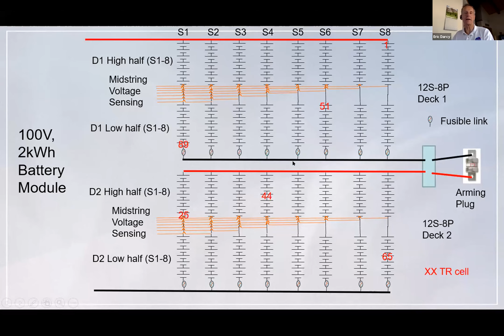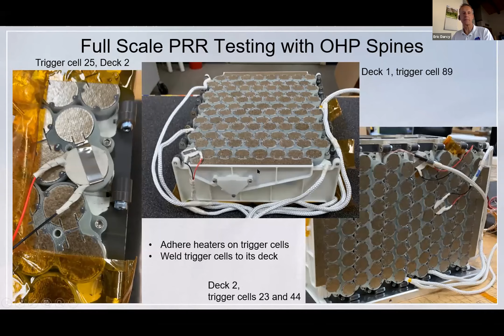As you can see here, we had mica covers on top of every cell, so that when the trigger cell goes into thermal runaway, it blows through its mica cover, and mica is a very high temperature material, so the adjacent cells are protected from the ejecta. And here's our little homemade heater to heat up the trigger cell in order to drive the thermal runaway response without heating all the other cells.